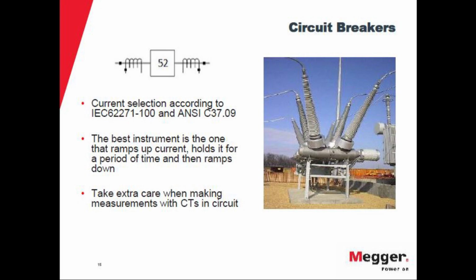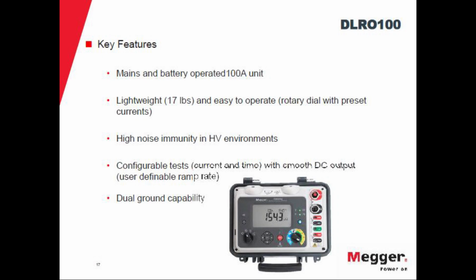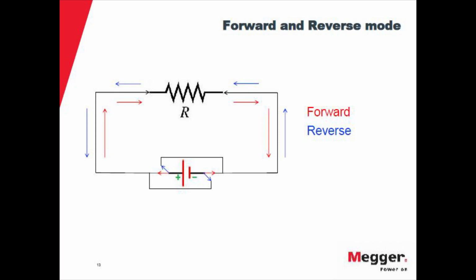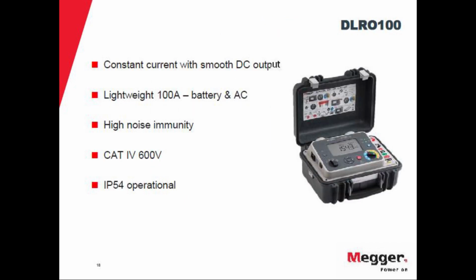For that, you have to use an accessory, which is a CT clamp, a current clamp, that will determine how much current is flowing to ground and subtract that from the actual current that the instrument is using. If we go back to the concept here, you're applying a current, and the instrument doesn't know if the current is going through the sample or not. So if there's another path for the current to flow, the instrument needs to know the real current going through the sample to be able to use Ohm's law and calculate it. So with an extra CT on this ground path, you can measure that current and determine the actual value going through the breaker, and you can test with the breaker grounded, which is a safer test.